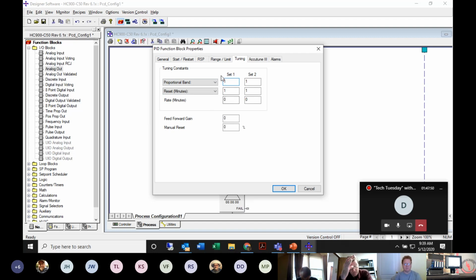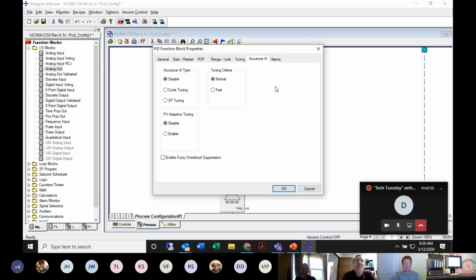Now, besides doing this, if you didn't want to manually tune it, you could come over to AccuTune. You can enable or disable AccuTune, and with one button push, you can tune the process and get it very close, if not right on, where you need to be for your tuning.